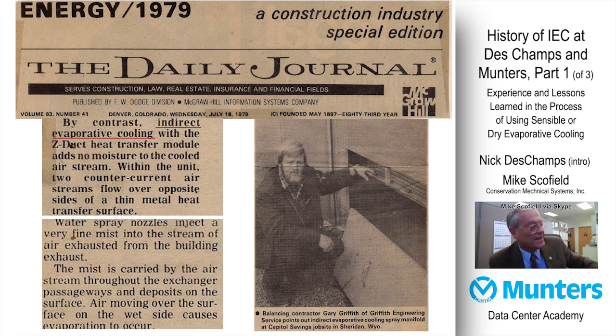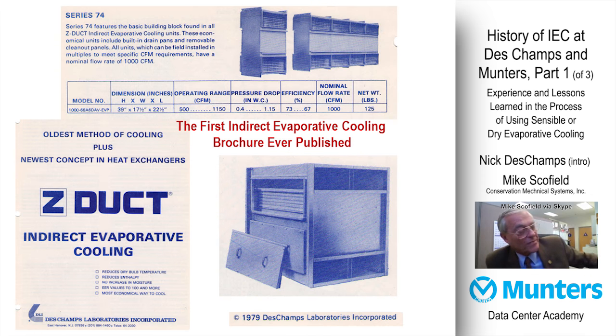But in any case, we learned our lesson in using a water spray on aluminum, and the lesson was that it definitely shortened the life expectancy of the indirect evap cooling heat exchanger. The first brochure that describes this concept, as far as we know, in the United States was shown on the next page there, and is the heat exchanger using the Series 74 same counterflow 1000 CFM modules, but coupled together in a larger manifolded heat exchanger section that allowed us to treat larger CFMs.